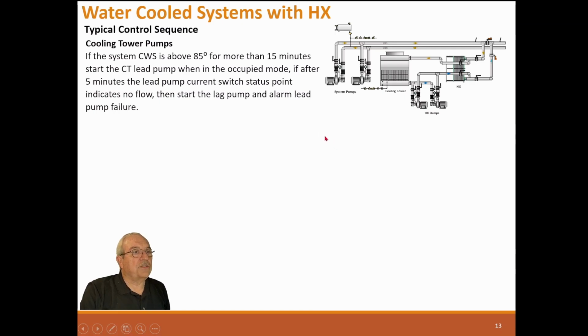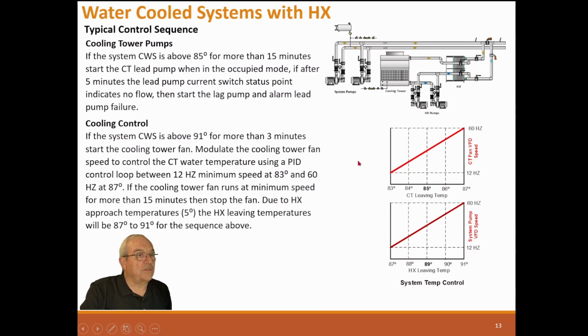Cooling tower pumps. If the system, that's these pumps here, the cooling is above 85 degrees for more than 15 minutes, start the cooling tower lead pump in occupied mode. And after 5 minutes, if the lead pump current switch status point indicates no flow, then alarm. Okay. For cooling control, if the system condenser water is above 90 degrees for more than 3 minutes, start the cooling tower fan. Maintain and modulate the cooling tower fan speed to control the cooling tower water temperature using a PID control loop between 12 hertz and maximum speed at 83 degrees and 87 degrees. If the cooling tower fan runs at minimum speed for more than 15 minutes, stop the fan. Now, note that due to the heat exchanger approach temperature of 5 degrees, the heat exchanger leaving temperatures will be 87 to 91 for the sequence above.